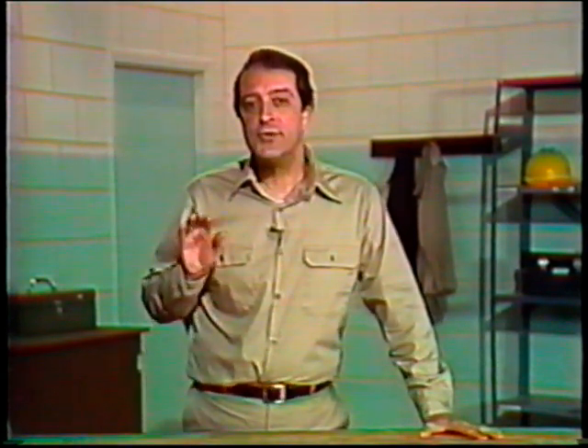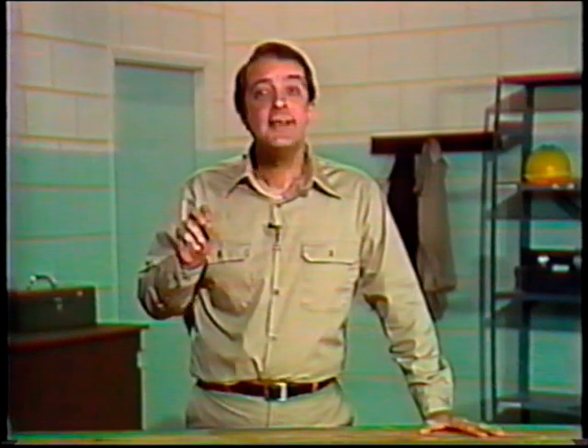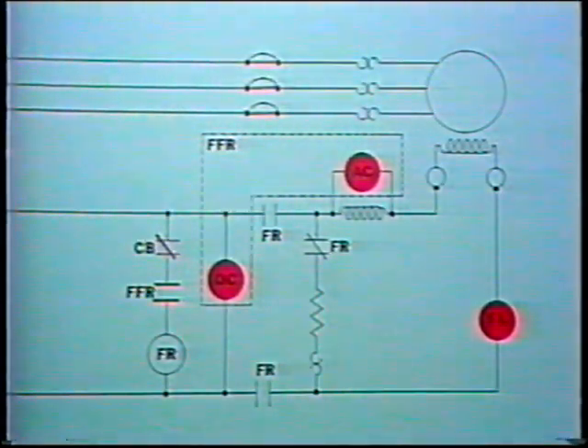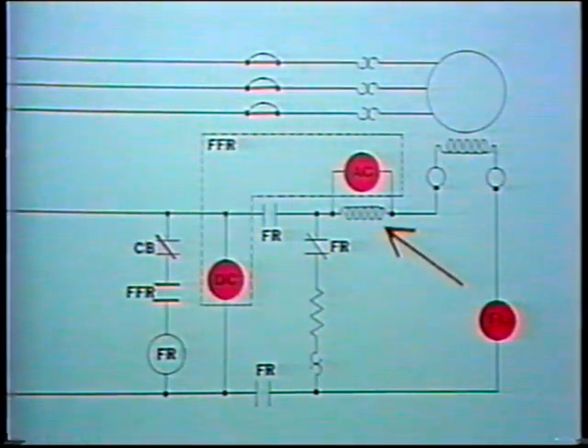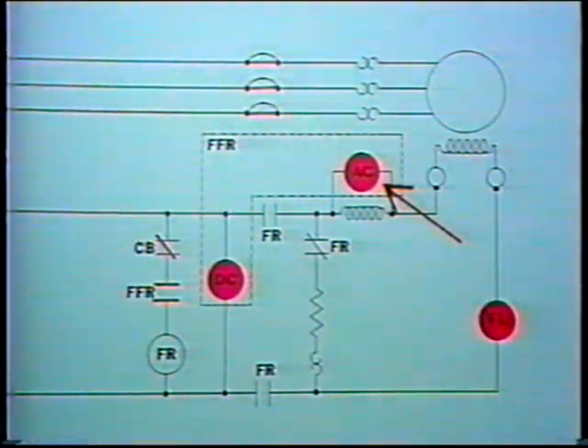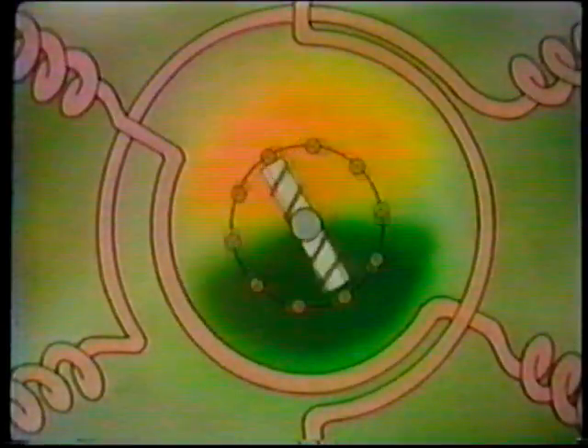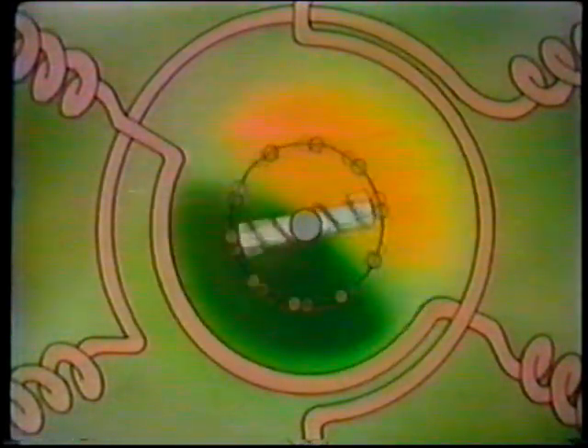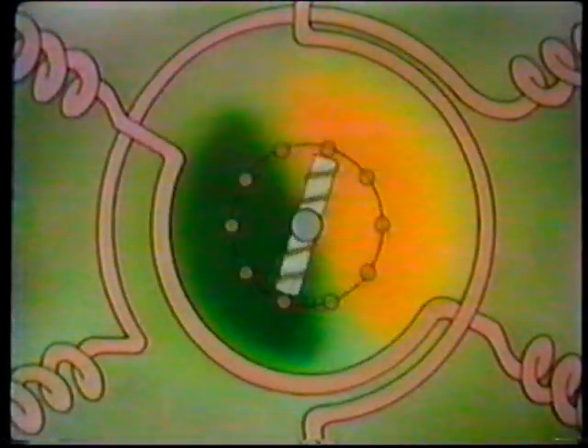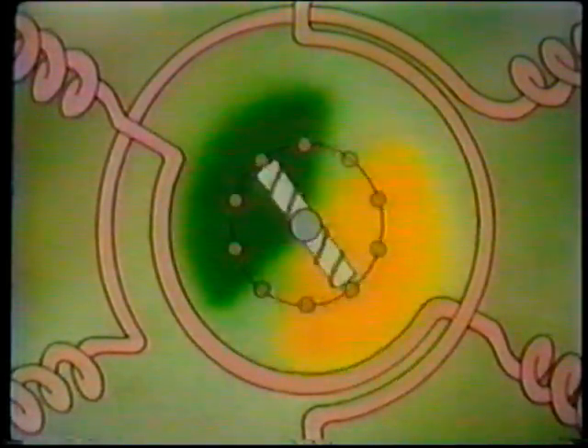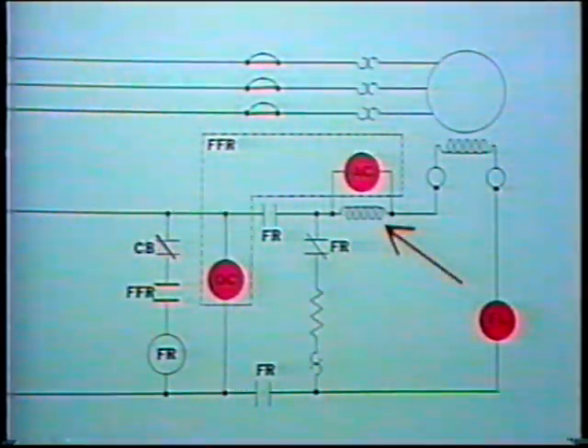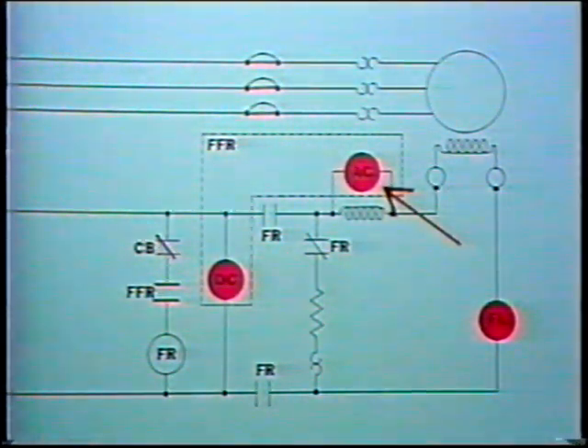So when the frequency of the induced alternating current is at maximum, such as it is at motor start, the inductive reactance of the inductor in the circuit is at maximum. That produces a large voltage drop across the inductor. The greater the voltage drop across the inductor, the greater the current flow through the AC coil will be. As the rotor accelerates closer to synchronous speed, the frequency of the induced alternating current decreases. The voltage drop across the inductor also decreases. That decreases current flow through the AC coil.